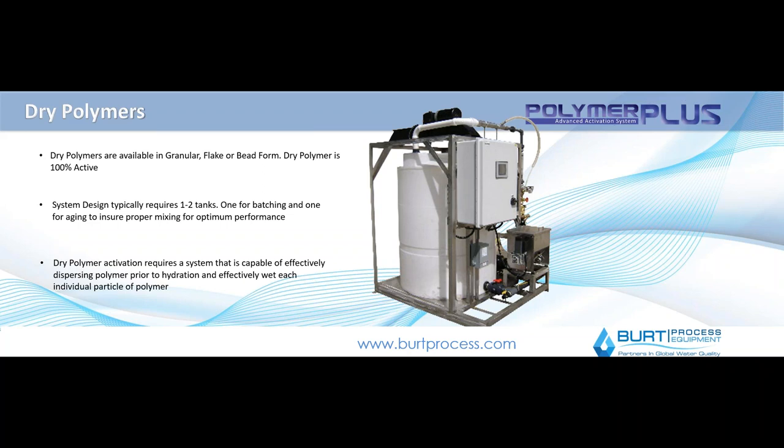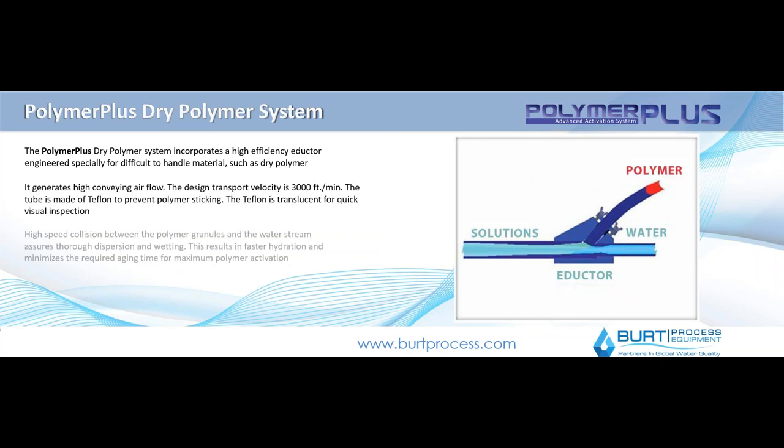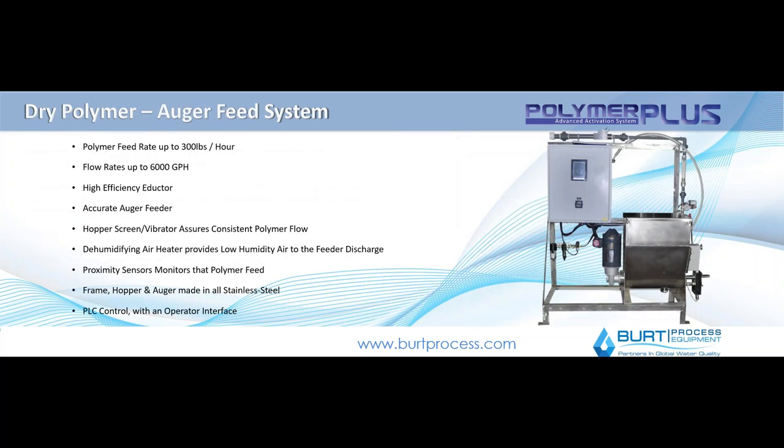Typically these are one or two tank systems whereby you have a means of transferring the polymer into a water solution in the tank for blending, aging, and transfer. There are a few different ways to do this. You can use an eductor-based system similar to how the activation chamber works, where you have an actual stream of water filling into your blending tank and the polymer is allowed to be injected dry and disperses through it into the tank. Or you can do more of a hopper or auger type device where the polymer is put in and transferred up through an auger-based system into a tank.